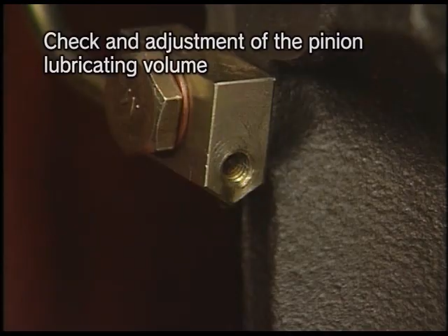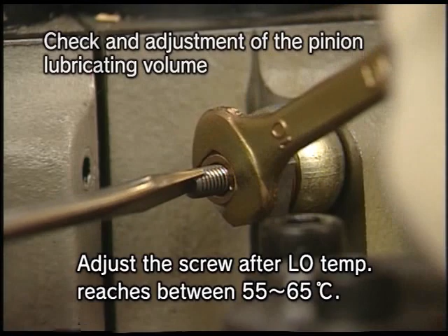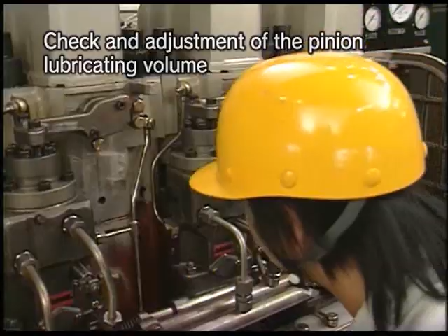If the feeding volume of lube oil does not meet the specified value, remove first the cap nut of the lube oil flow rate regulating valve, loosen the lock nut, and then screw in the lube oil flow rate adjusting screw until becoming fully firm. Gradually loosen the adjusting screw and make an adjustment in such a way that the oil drops at the rate of 1 drop every 10 to 12 seconds.